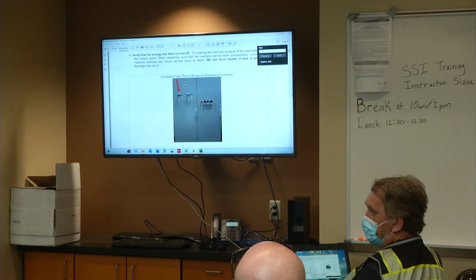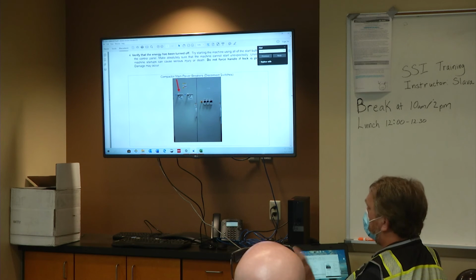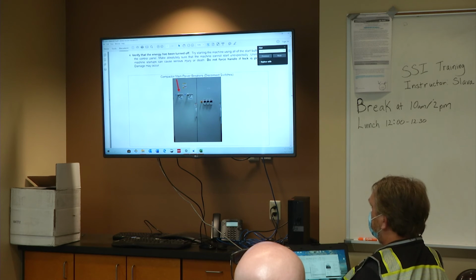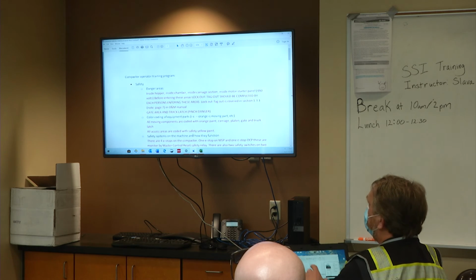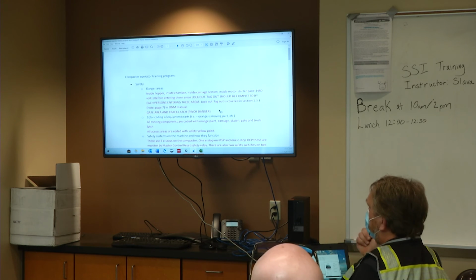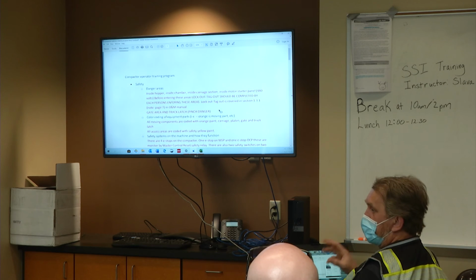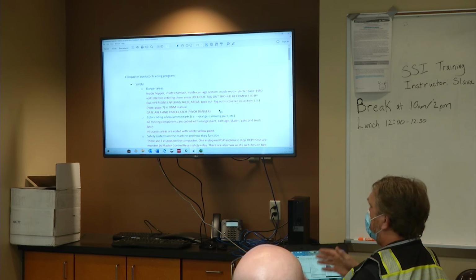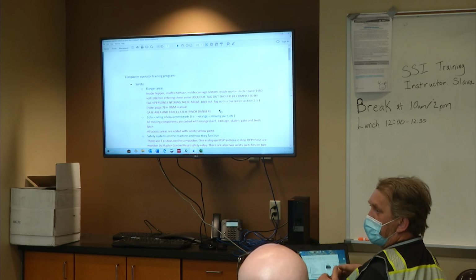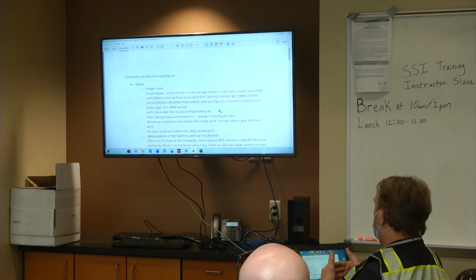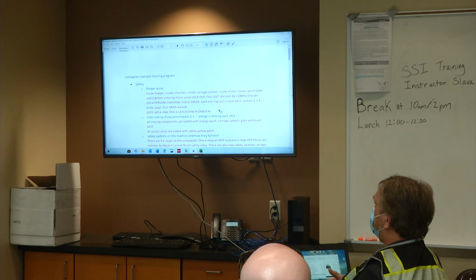If the drive faults out, on the HMI you'll get a generic fault like a VFD fault. To get an actual reading, you have to go down to the motor starter panel and see what the actual fault is. So basically, to gather information, if you get a VFD fault, go back to the motor starter panel, take a picture, collect as much information as you can, and send it over to me. My job in the office is service and technical support.